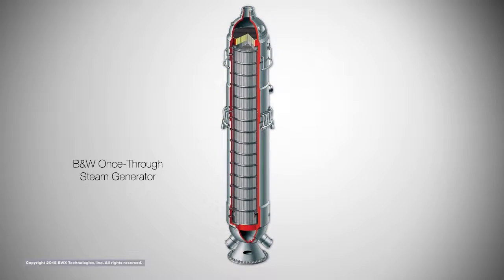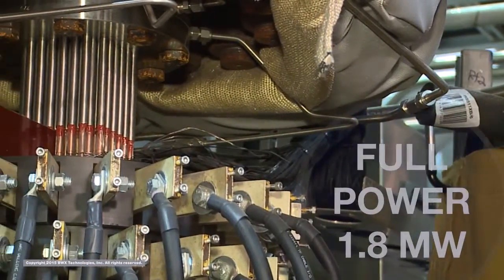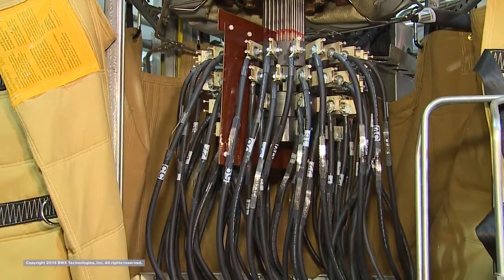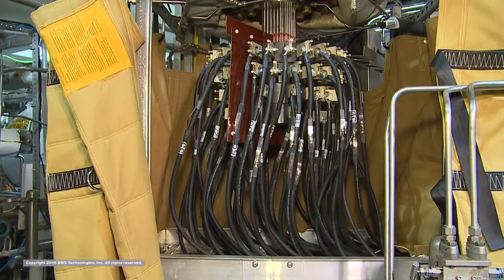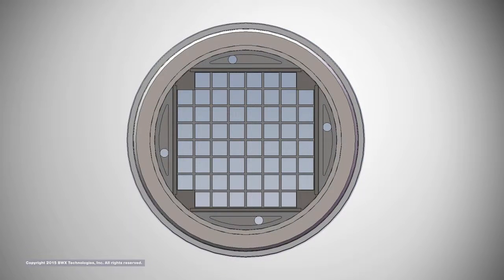The 19-tube design effectively sets the minimum power requirements. The IST design at full power is 1.8 megawatts. While the system is heated with electricity rather than nuclear material, a nuclear core is faithfully simulated. There are 60 heater pins arranged in an 8x8 array with 160 thermocouples.